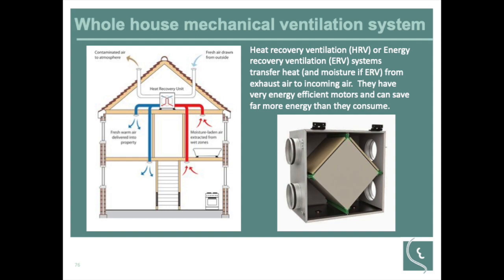Something else that this can also provide some benefit to, if anyone does sealed crawl spaces, is that this HRV or ERV can pull the air from the crawl space to exhaust and use that as my exhaust air leaving the building. So my crawl space will actually be a little bit negative to the house, and air will flow from the house through the crawl space and then out. That is something we have seen before: if you seal the crawl space well, then if any moisture gets in there, it gets kind of stale and stagnant and things aren't good.